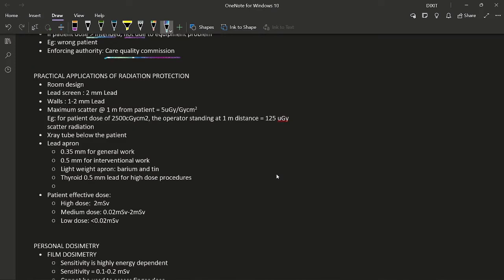Some practical applications of radiation protection: the room should be properly designed; the lead screen protecting the operator should have 2 mm of lead; walls should have 1–2 mm of lead. Maximum scatter at 1 meter from the patient is 5 microgray per gray·cm². This means that for a dose-area product of 2500 cGy·cm², an operator at 1 meter should receive a maximum of 125 microgray of scatter radiation. Placing the X-ray tube below the patient directs scatter radiation toward the operator's feet, reducing irradiation of more radiosensitive organs.